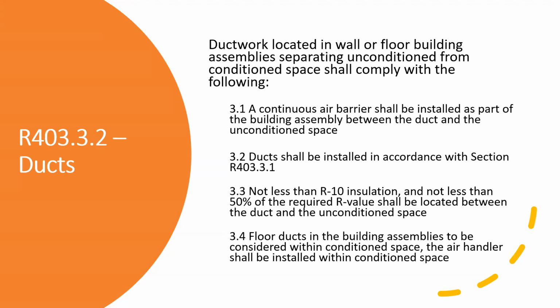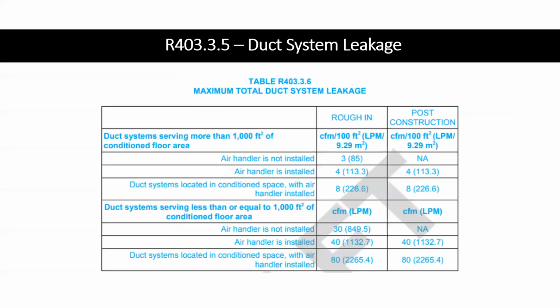I know it's going to be misread where they say R10. They'll have an R10 or an R13 and they'll put it in there and it will be completely crushed at the point of contact. That's not acting effectively as an R10 or an R13. It no longer has that R value because it's crushed. There really needs to be allowance of spacing to allow at least a minimum of R10 to be in between that duct and the exterior envelope.